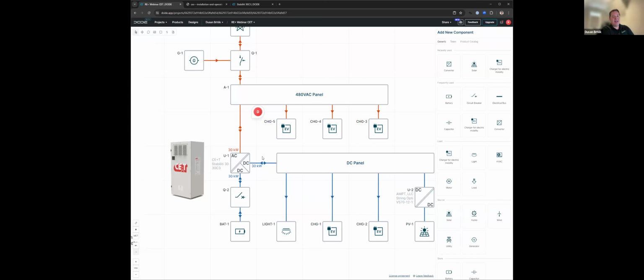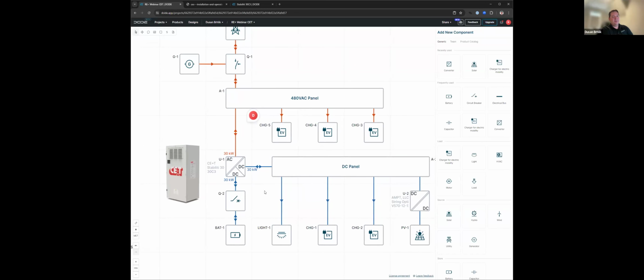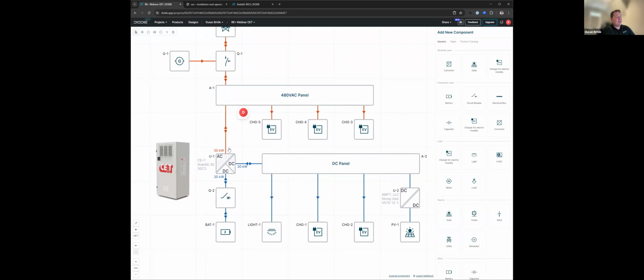So this air gap, if you will, is extremely important. One of the design principles that really needs to be taken into account early on is grounding—very, very important. You can really destabilize your system and make it unsafe. When you have this air gap, or galvanic isolation like the Stabiliti, it allows you to have a flexible system—if you have a mismatch in grounding between AC and DC side, it's still okay to deploy. But you guys have deployed this galvanic isolation in a unique way. It's not just a big copper coil in a converter—your converter is fairly compact in size.